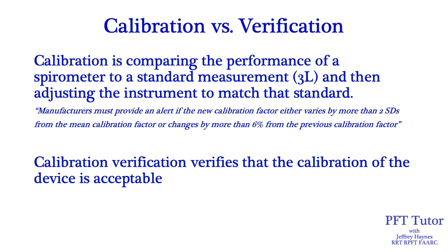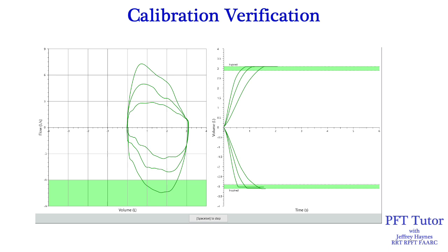Calibration verification is what most people are doing first thing in the morning. Cal verification is verifying that the calibration of the spirometer is acceptable. When you are calibrating the spirometer, you are teaching the software that this is 3 liters with each stroke of the syringe. But when you are performing verification, you are asking the question: is this 3 liters?